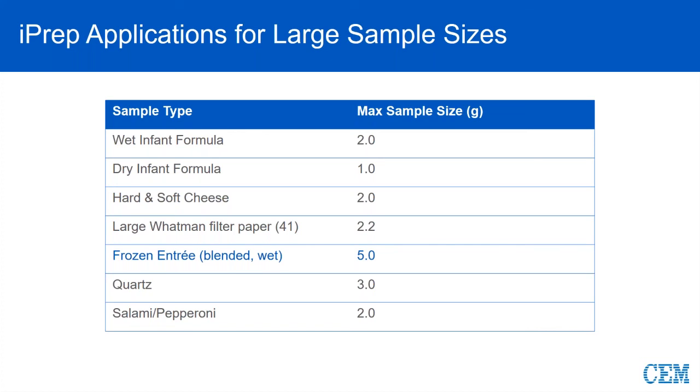For example, wet and dry infant formulas, and a frozen entree where we literally took a frozen dinner, put it in a blender, and weighed out five grams — probably half of that is water weight — and it digested fine. We also have a customer that does high-purity quartz. Salami and pepperoni are very high fat content, so being able to do one and a half to two grams is actually a pretty big deal based on the fat content and how much pressure it generates.